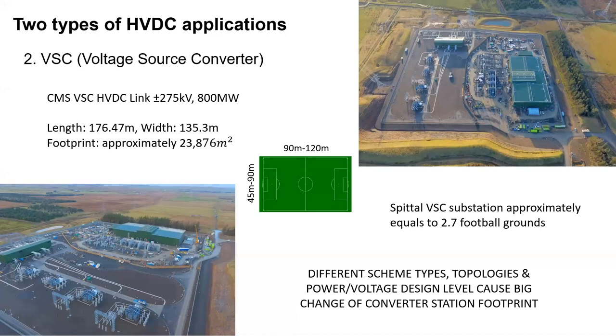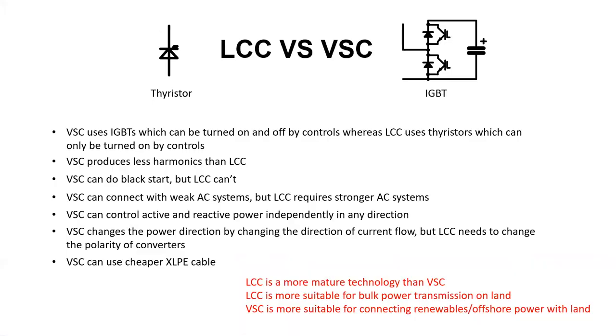It can also be seen that the DC voltage for this particular layout is not 600 kV. It's only 275 kV. But if the voltage was 600 kV, the space required for VSC application would still be lower than LCC. The other differences between LCC and VSC are just the type of devices these applications use.